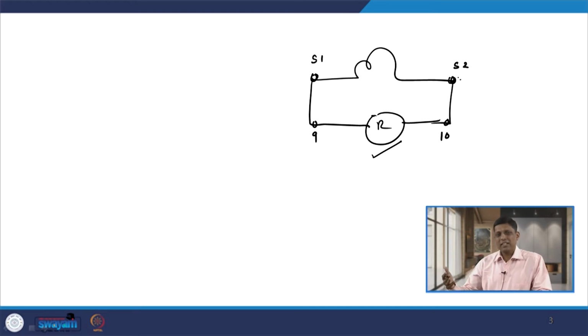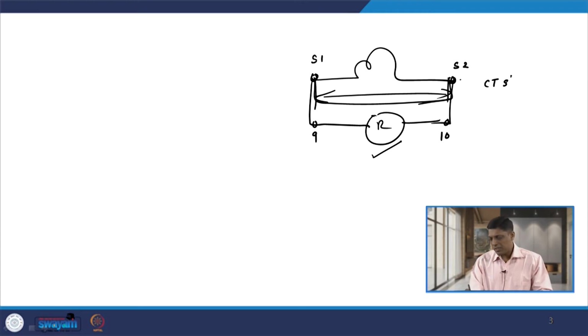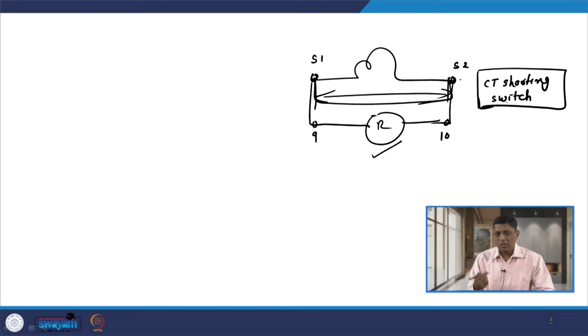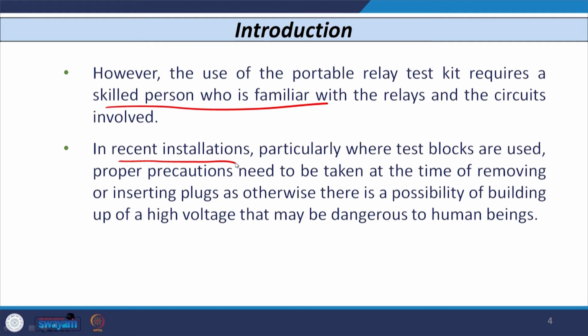When you remove it, the CT secondary would be open circuited. Whenever the CT secondary is open circuited, a huge voltage is developed across it, which may endanger the life of the person working as an operator in the substation. To avoid that, whenever you remove the relay, you have to short the secondary of the CT, because the CT secondary should not remain open circuited. This is done by a CT shorting switch. Most digital or numerical relays provide this device, known as a CT shorting switch. Whenever you remove the relay from the panel for testing, the CT shorting switch comes into the picture and automatically shorts the secondary of the CT. So, there should not be any problem as far as open circuiting of the CT secondary is concerned. So, this is one of the precautions.